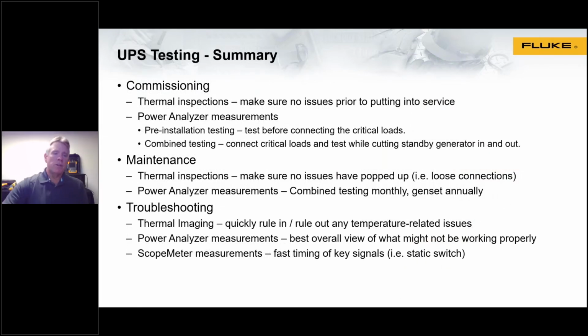So in summary, there are different modes of UPS testing. One certainly would be commissioning, and then ongoing maintenance, and also troubleshooting. And in each category, there are certain tools that are very useful. Some, like the thermal imagers, are useful in all three phases. So in the commissioning phase, making sure there are no issues, making sure you have no improper heat or loose connections or hot connections or imbalance or overload conditions.